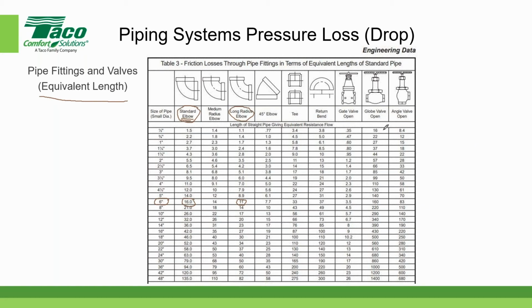Now, the other thing I wanted to point out, if you'll notice, I have a gate valve in this chart. The gate valve has an equivalent length of straight pipe of 3.5 feet. But the globe valve right next to it has an equivalent length of 160 feet. So if you have a globe valve in your system, the pressure drop associated with it is quite high. Out of all the different fittings shown here, the globe valve has the greatest equivalent length of straight pipe. In other words, the pressure drop across the globe valve would be the same as you would find in 160 feet of straight pipe. Again, in our case, 6 inches. And again, you can download these charts from the internet. They're readily available. This is in equivalent length of straight pipe, and that's in feet.